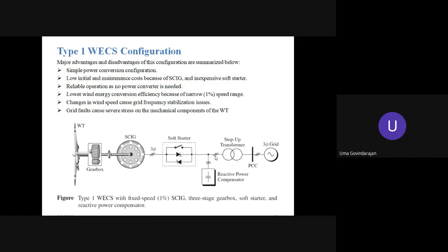Okay, now let us look at a simple flow diagram. Understand that the rotor of the wind turbine is connected to the rotor of the machine. Whenever the machine starts rotating, for the building up of the voltage, the machine will draw reactive power from the grid. So that's why I was mentioning the reactive power in the previous slide. For building up of the shunt magnetic field, the machine will draw the reactive component from the grid.